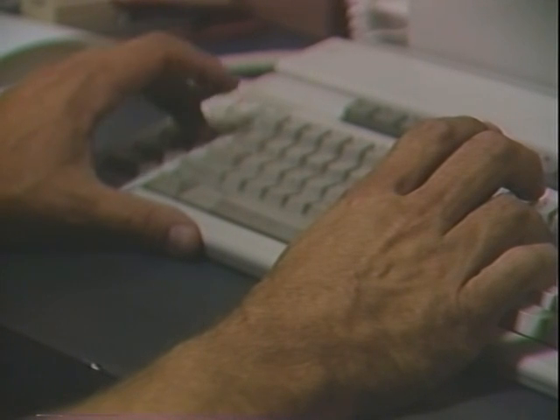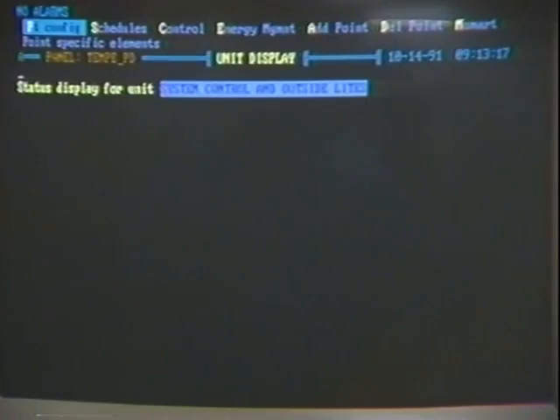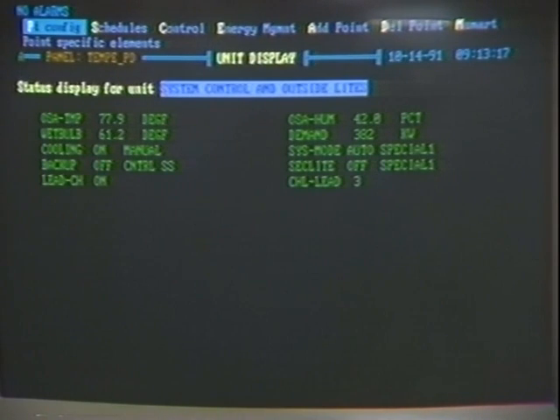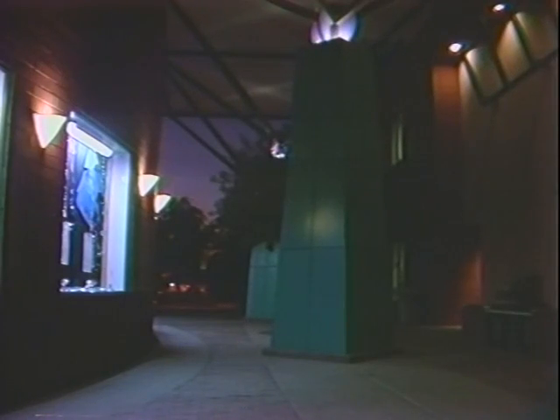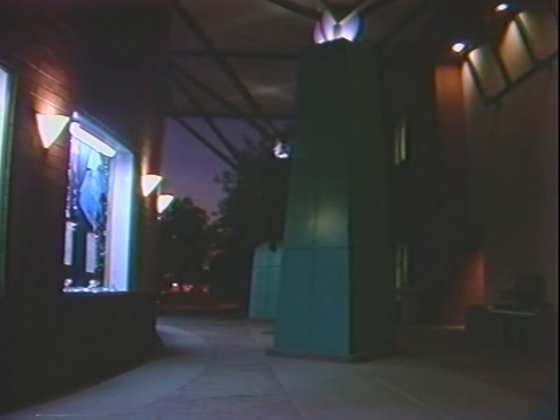For each building, an operating schedule is entered into the system. The computer then maintains proper building climate during the scheduled time, and exterior lights are turned on only from dusk to dawn. This scheduling system ensures that energy-hungry devices operate only when necessary. The target advantage from any building automation system is to save money.